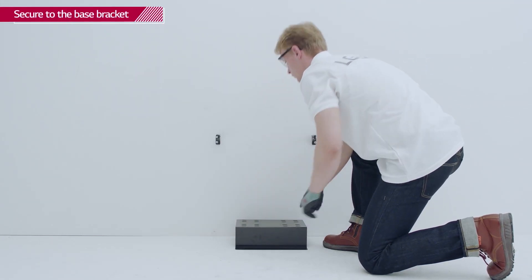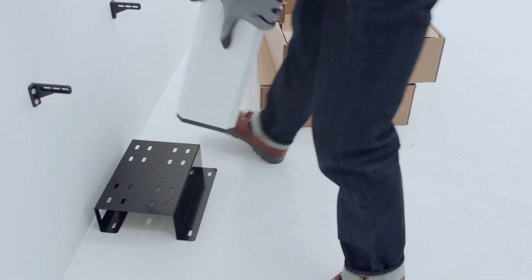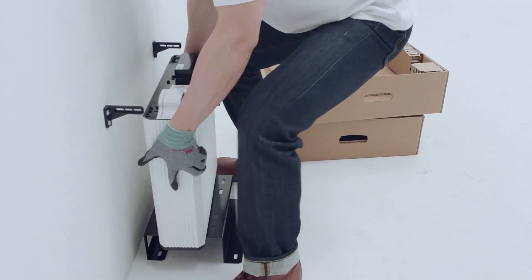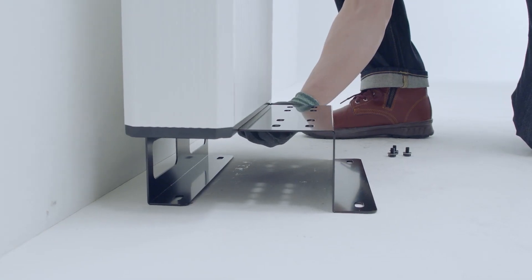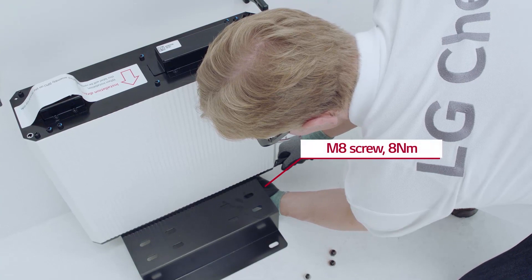Put the base bracket to the wall and place the first battery module on top of the base bracket. Then fasten it with M8 screws with a torque of 8 Nm.